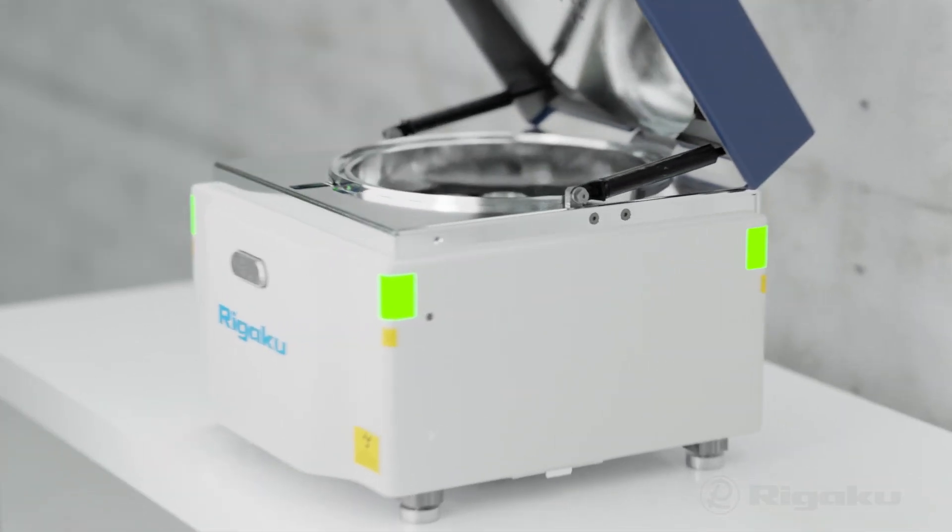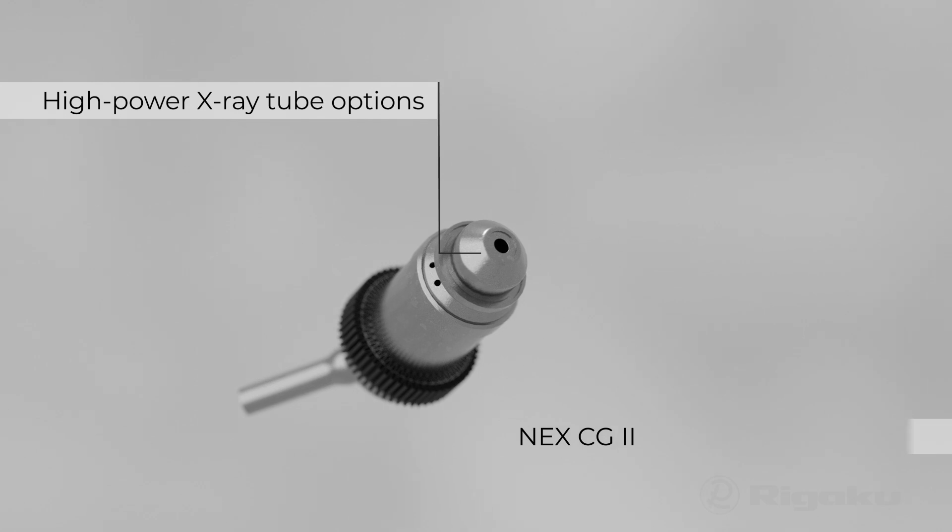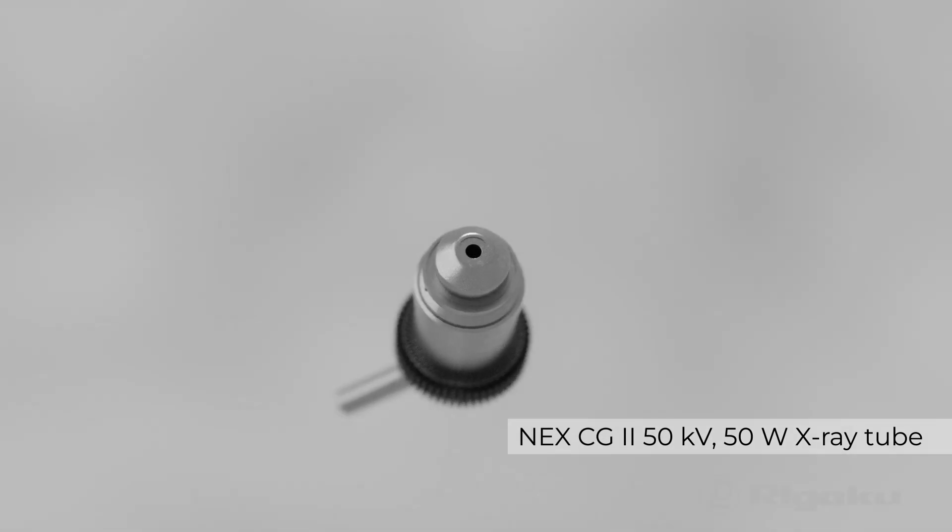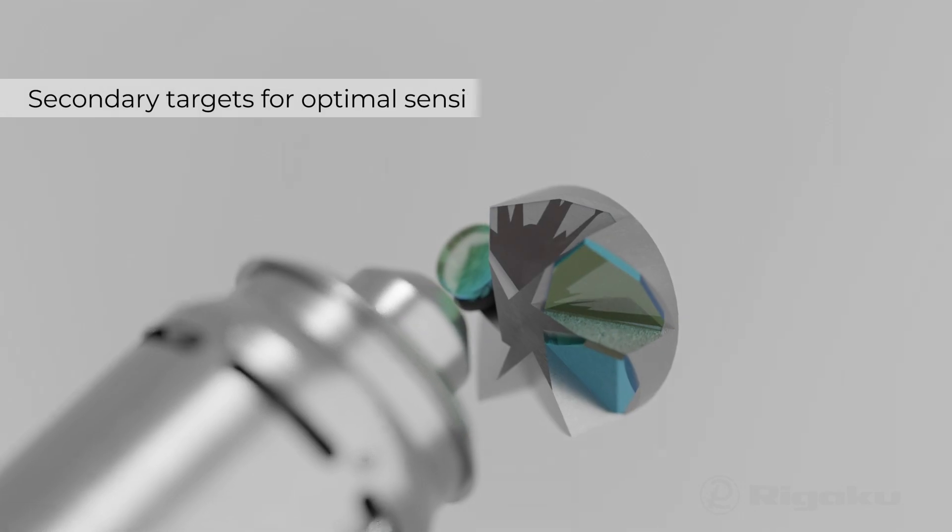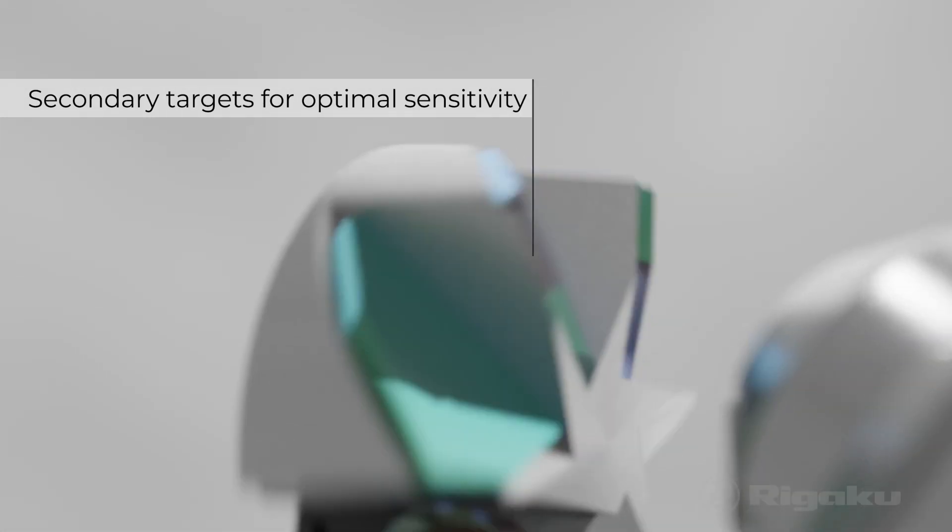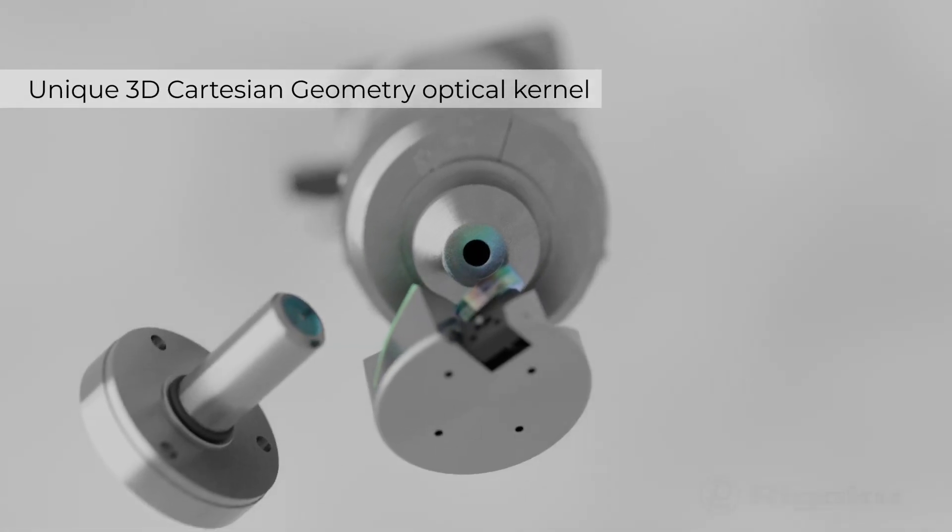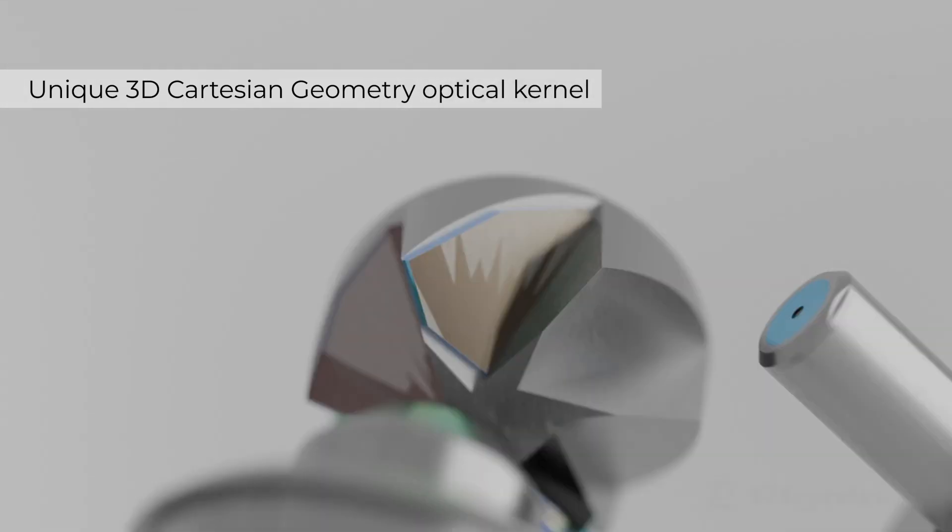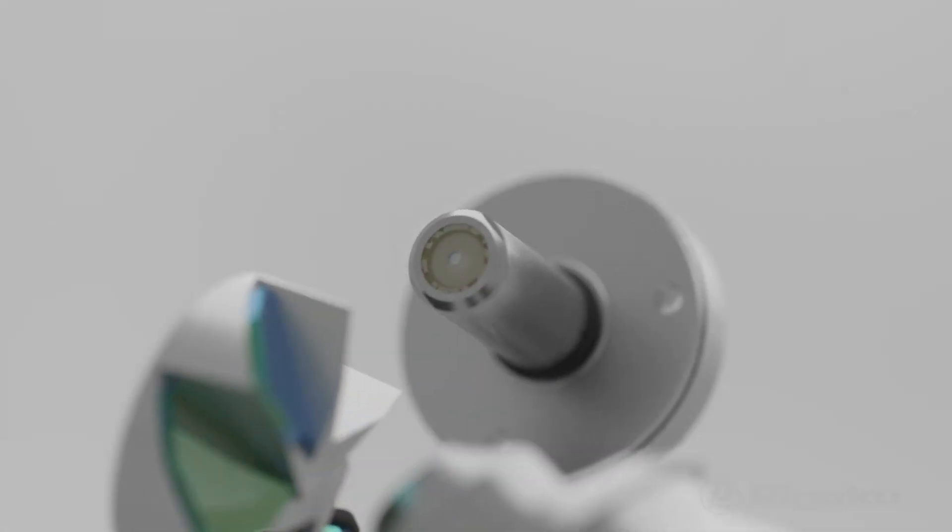NEXCG2 achieves this and more with an end window palladium anode X-ray tube in either a 50kV 50W or a 65kV 100W option. Monochromatic or polarized excitation from five secondary targets and a high performance large area silicon drift detector acquire a spectrum with virtually no background noise using full 90 degree Cartesian geometry and indirect excitation.